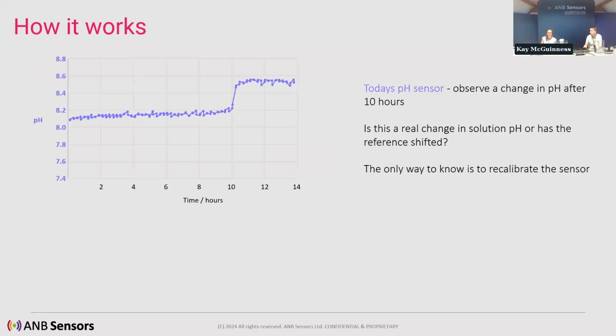Okay, so we'll jump straight in to how the sensor works. Maybe Nathan, you can do this bit. Yeah, that's fine. So how does it work? When we started ANB Sensors, we went out to speak to glass pH electrode manufacturers. I'm sure you're aware of those, deployers and users of the glass pH. And we really wanted to understand why those glass pH electrodes needed to be recalibrated. Overwhelmingly, the response was it's due to reference electrode drift and reference electrode changes during deployment, which are unknown and only corrected during a calibration process.